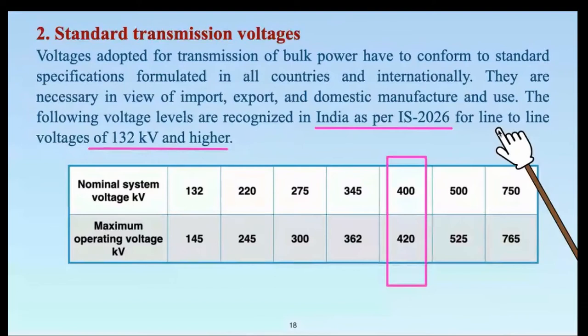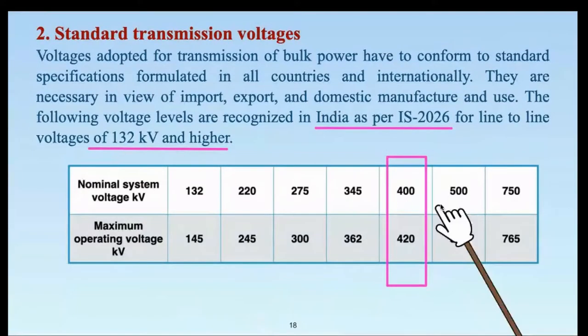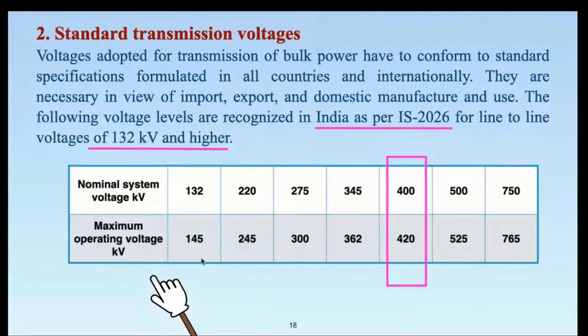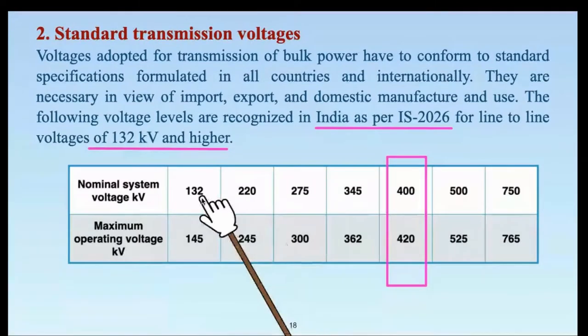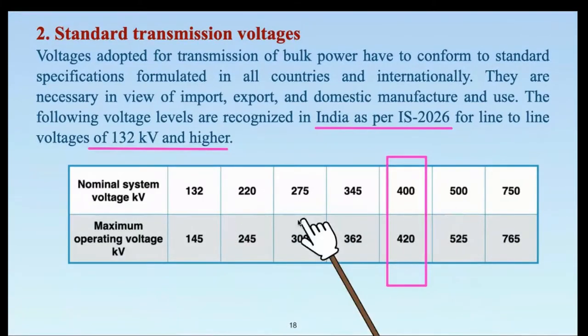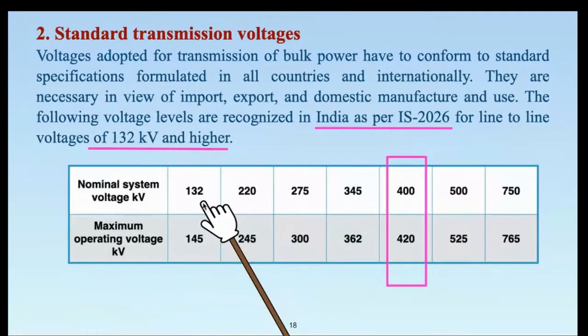In Nagpur, there is a load dispatch center which receives 400 kV power at one particular center and then distributes it across the city. Several generating stations are connected at this voltage to the load dispatch center on Amravati Road. After 400 kV, there are three or four 220 kV substations in Nagpur, and then around 12 to 15 substations at 132 kV. Stage-wise, distribution takes place from one large transformer to four major centers, then sub-centers, with voltage reduced to 11 kV and then 440 V at the consumer end.